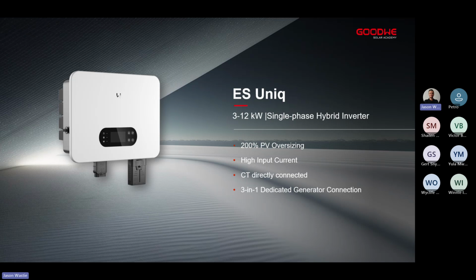So in 12 years, we've improved on the product and made sure that it stays market relevant and has the correct features and functionality for you as either the installer, distributor, or homeowner. If we look at some of the key features for the inverter, we'll go through some of those today. One of them is 200% PV oversizing, high input current on our MPPTs, as well as being CT directly connected, meaning that we don't need a physical external smart meter. We use the CT connected directly to the inverter, and we'll get all of our grid references from that. We also have a 3-in-1 dedicated generator connection, or dedicated generator port, that we can use in 3 different ways, and we'll go through that when we touch on the key features coming up.